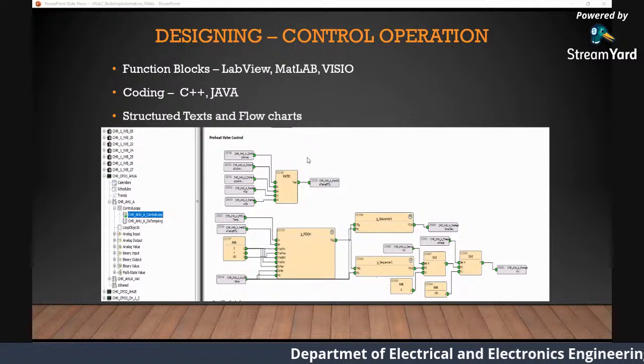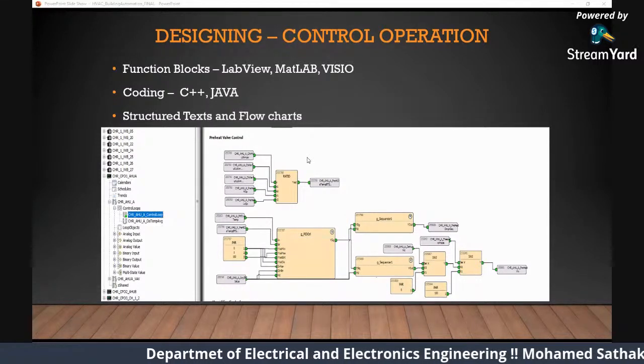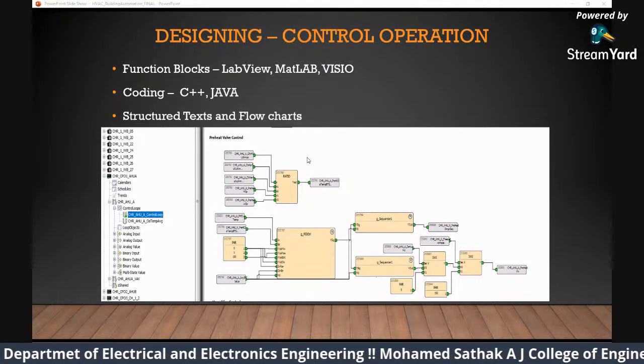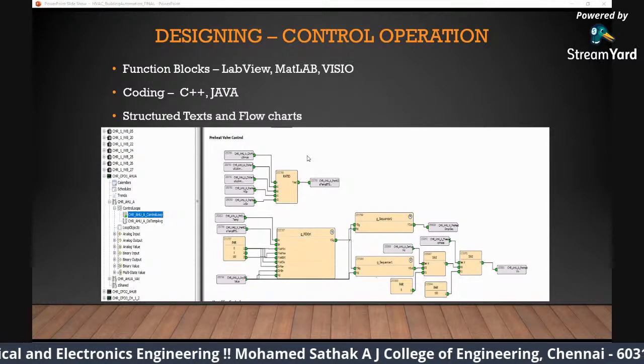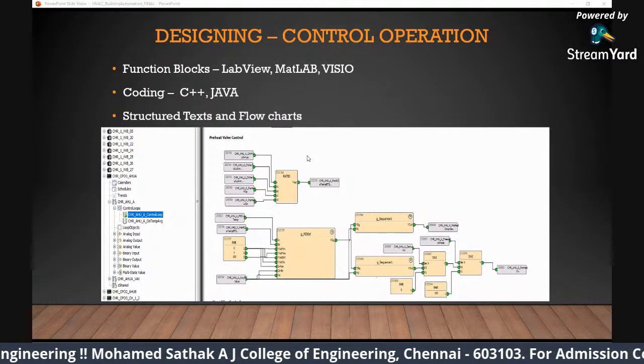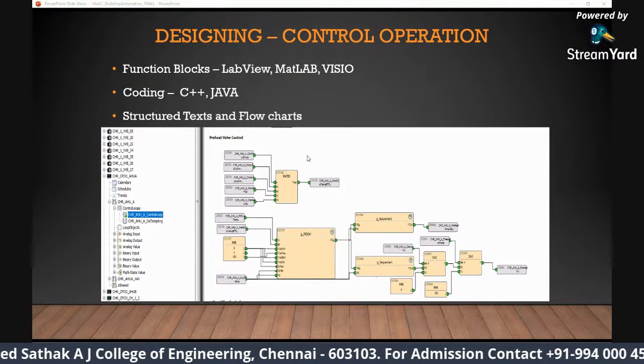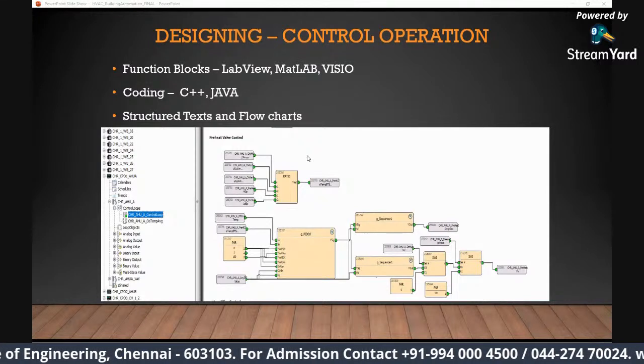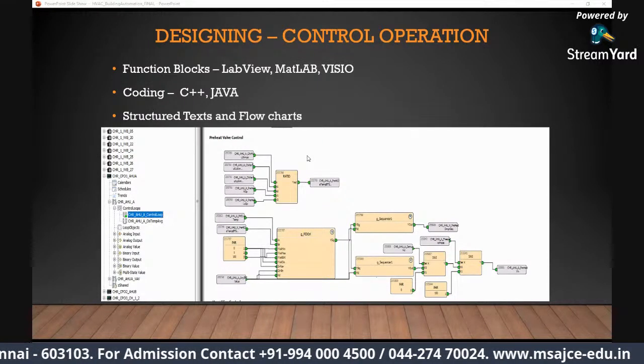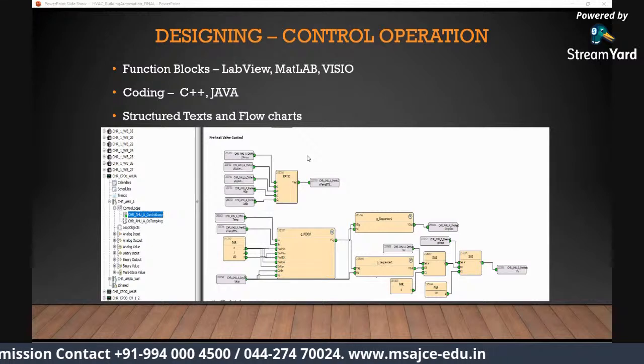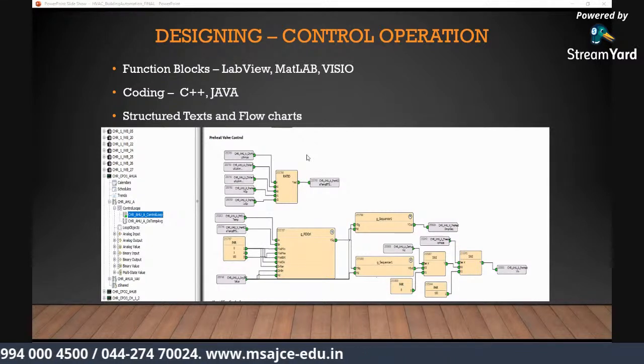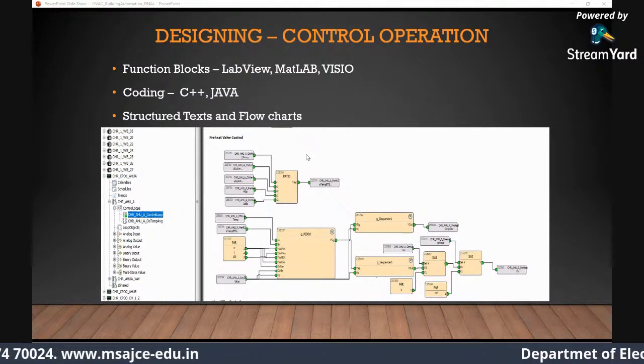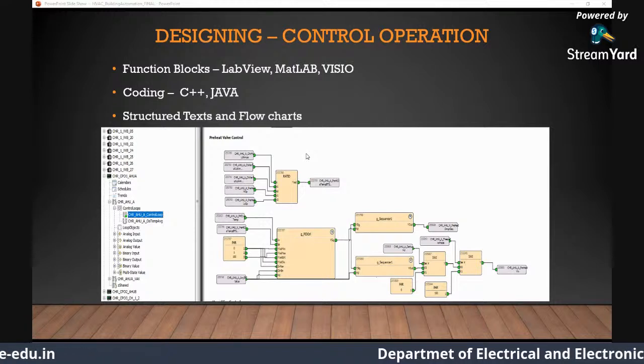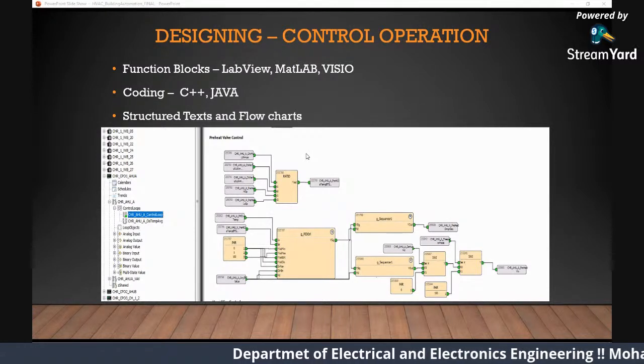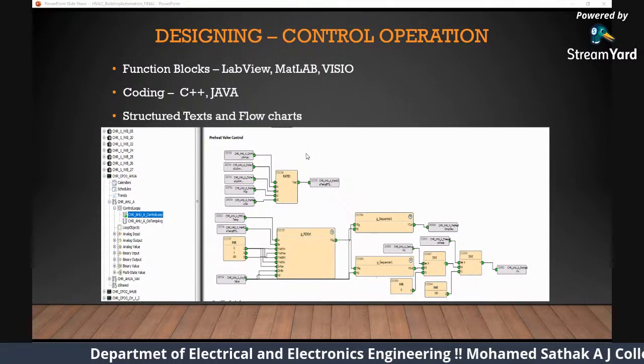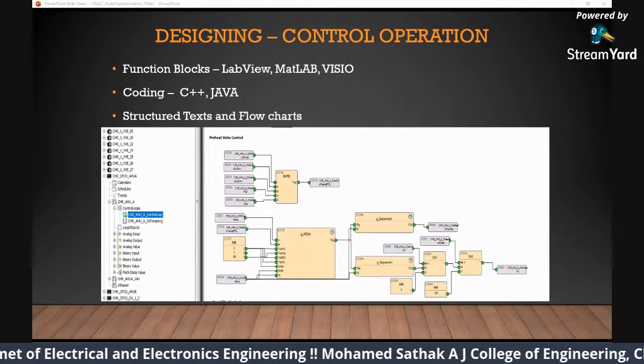Is there any specific recommended control system like ABB, Siemens, Allen Bradley, only which this HVAC platform works without any breakdown? Not really. Every HVAC system is good. It depends on the client. Let's say the client says I want ABB, I want Siemens, I want Honeywell. Let's say there's a new building under construction. During construction, they will bid for the automation system. So multiple vendors will bid for the project. Honeywell, Siemens, ABB, Schneider, whoever gets the bid, they will provide the automation system. That's how it works. Okay.